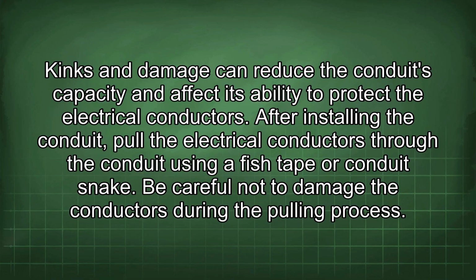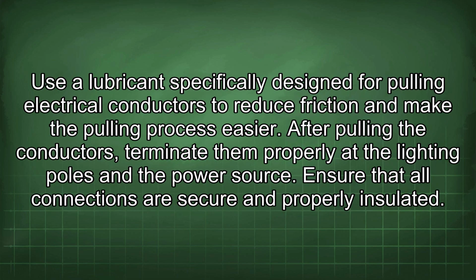After installing the conduit, pull the electrical conductors through the conduit using a fish tape or conduit snake. Be careful not to damage the conductors during the pulling process. Use a lubricant specifically designed for pulling electrical conductors to reduce friction and make the pulling process easier. After pulling the conductors, terminate them properly at the lighting poles and the power source. Ensure that all connections are secure and properly insulated.